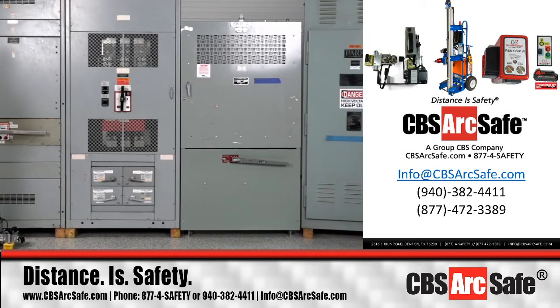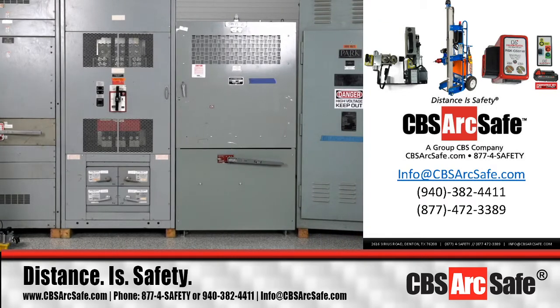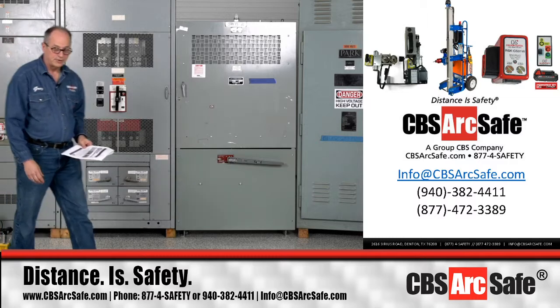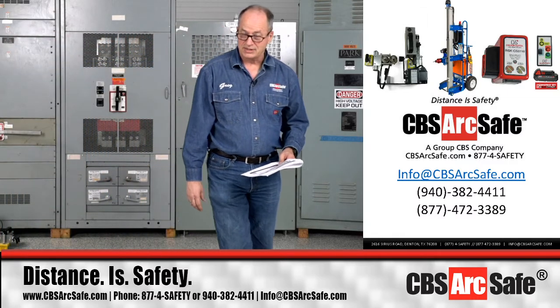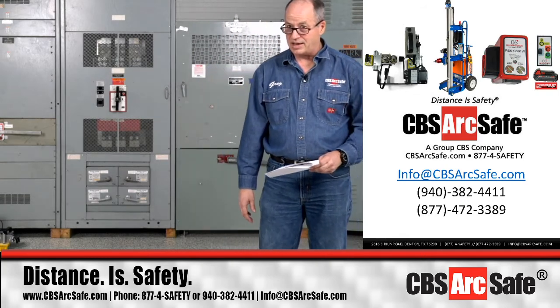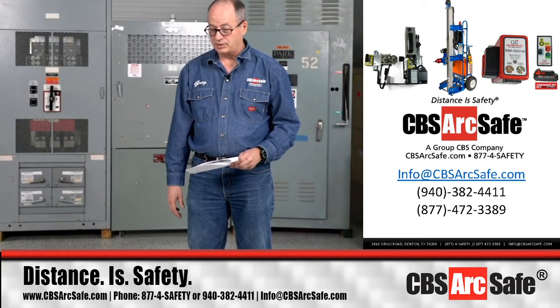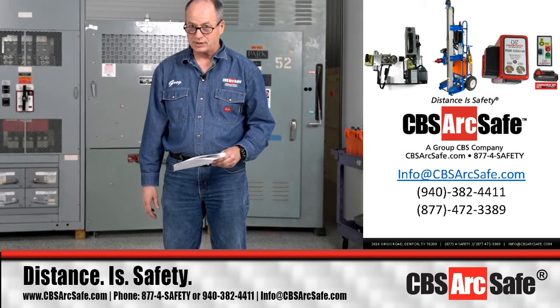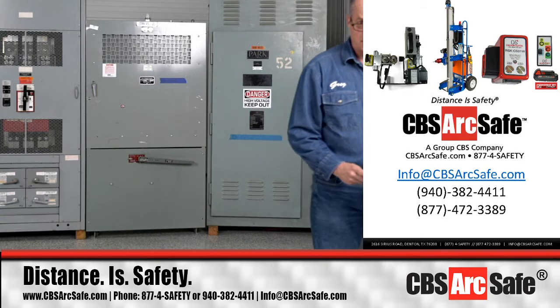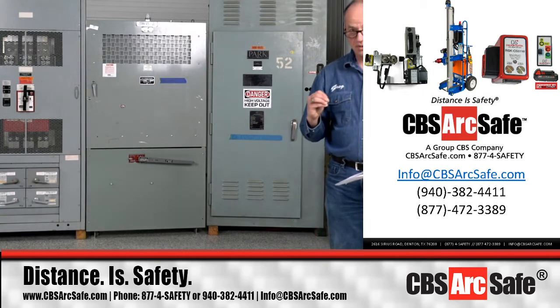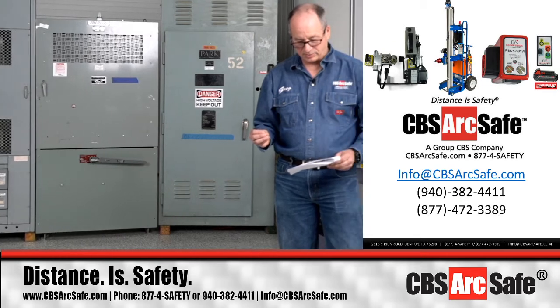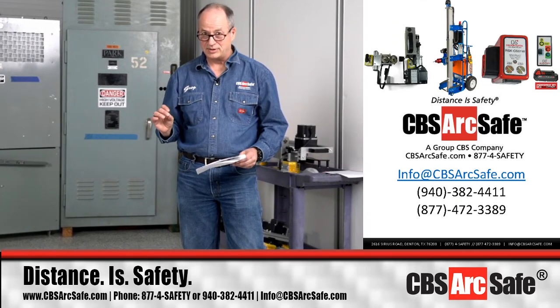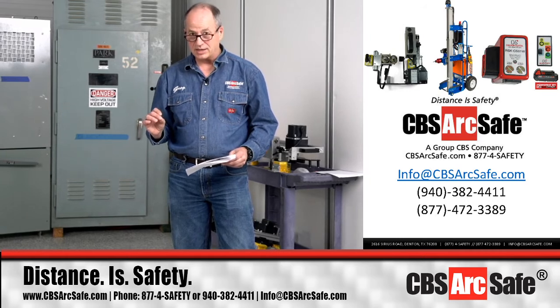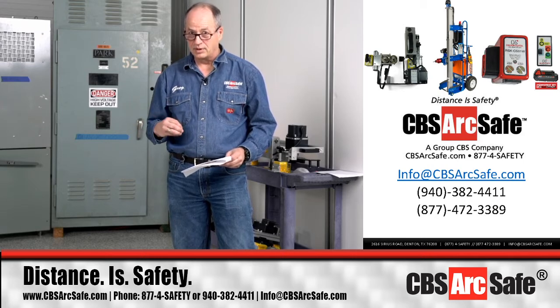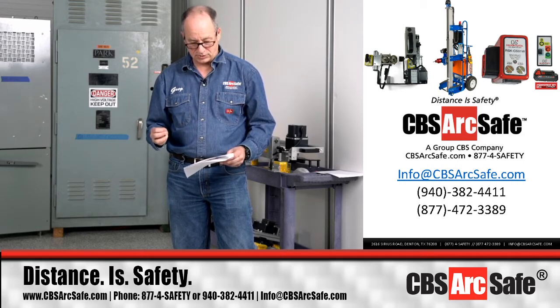They manufacture replacement vacuum interrupters. They have vacuum interrupter testing with what's called a MAC TS4, which measures the amount of vacuum in the vacuum interrupter, and they have the vacuum interrupter test set, which measures vacuum integrity so you can tell the quality of the vacuum within the interrupter. They have circuit breaker contact timer testers, and they also do SF6 interrupter repair, where they can recover the SF6 from your interrupter, refurbish it, and give it back to you to put back in service.